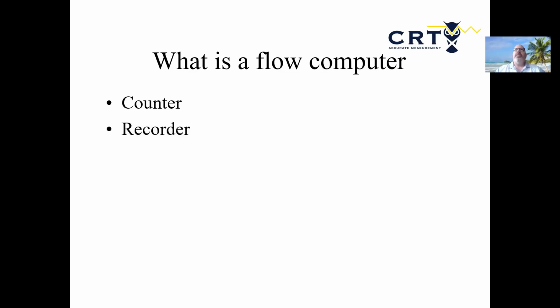It's also a recorder. It records events that happen within your measurement system and the devices connected to it: temperature, pressure, density. You can have chromatographs, tank levels, provers. One requirement of a flow computer is that it records events, alarms, and changes made to it, either by programming or process conditions, and keeps them in an audit trail for a certain amount of time, so we can go back and see what happened, and possibly make corrections if something went wrong or was entered incorrectly.